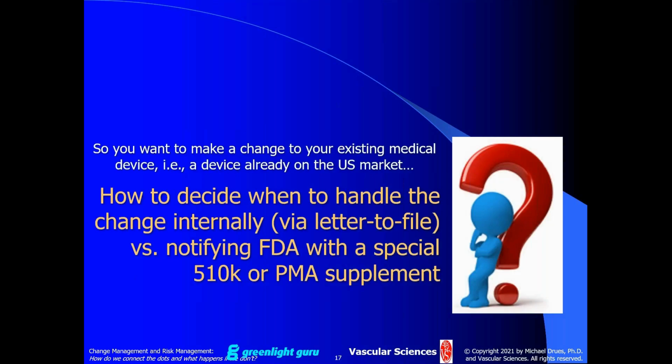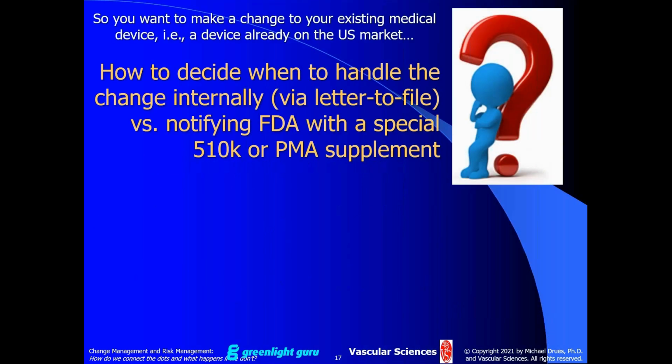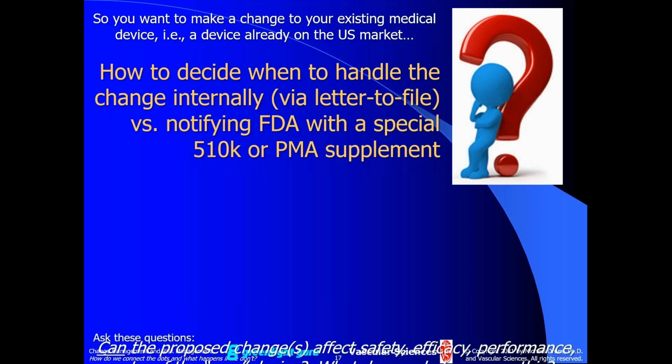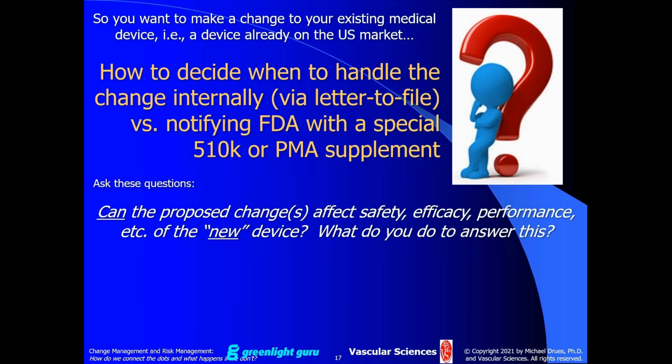So if you want to make a change to your existing device, in other words, a device that's already on the market, how do you decide how to handle that change internally? In other words, do you keep this internal to you via a letter to file, or do you notify the FDA either with a special 510K or perhaps a PMA supplement? Well, at a very, very high level, the questions to ask are, can the proposed changes affect the safety, efficacy, performance of this product? In other words, as soon as we change the device, in essence, we now have created a new device. And so are those changes significant enough to potentially change the safety, efficacy, performance?